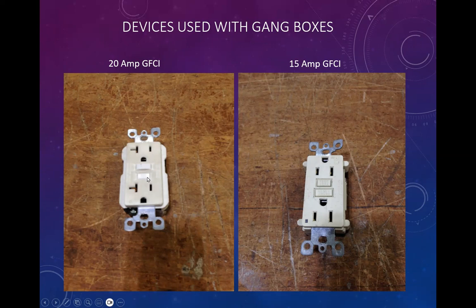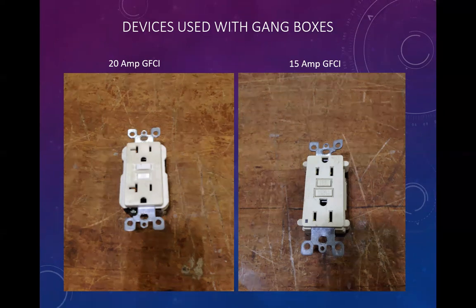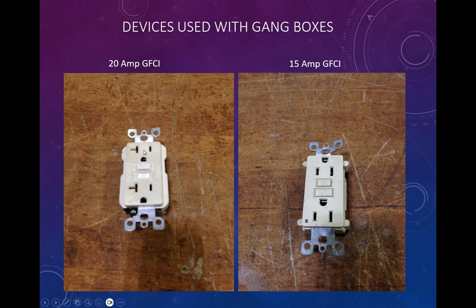For a load, like for example a wall-mounted air conditioning unit, most of those are pulling 20 amps, and the load is not asking, "Excuse me, mister, can I have 20 amps?" No, it says, "I'm going to draw 20 amps, whether you can give it to me or not." So if you plug it into a circuit that is only capable of providing 15 amps, it's going to overload that, and the circuit breaker is going to flip. So you need to up the ampacity by installing a receptacle with a different footprint, and you need to run a wire that is capable of handling 20 amps instead of 15 amps. So the wire has to be thicker, and the gauge would be 12 at least.